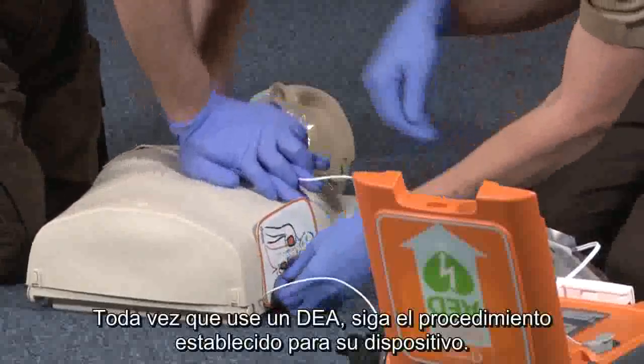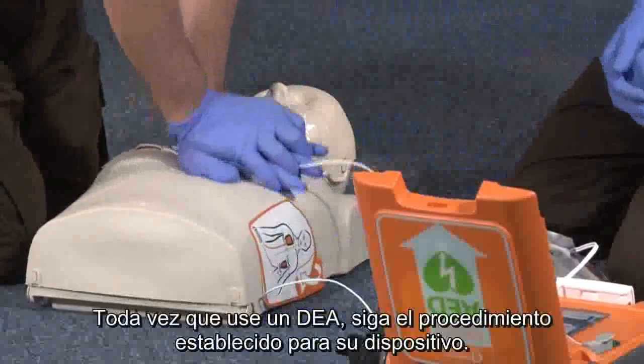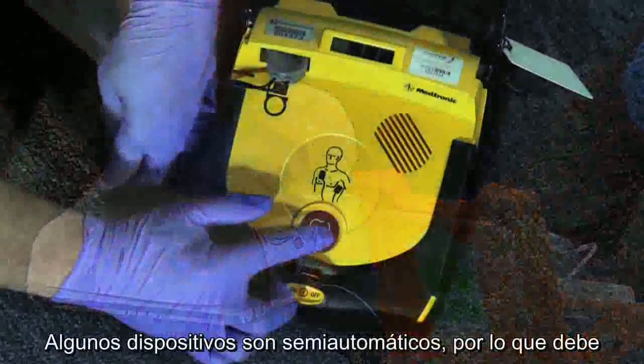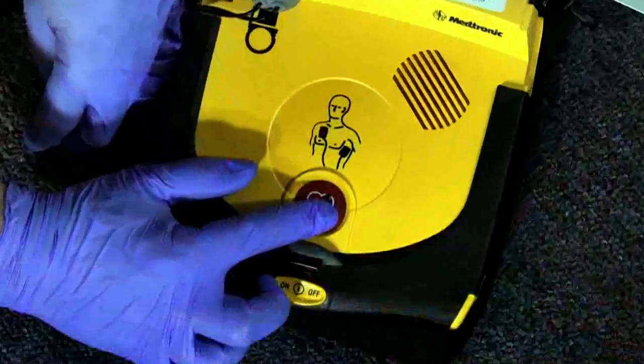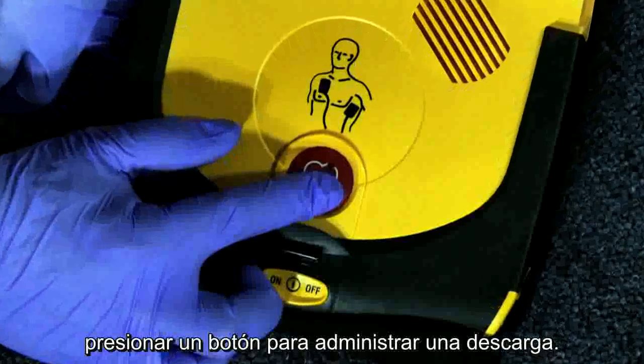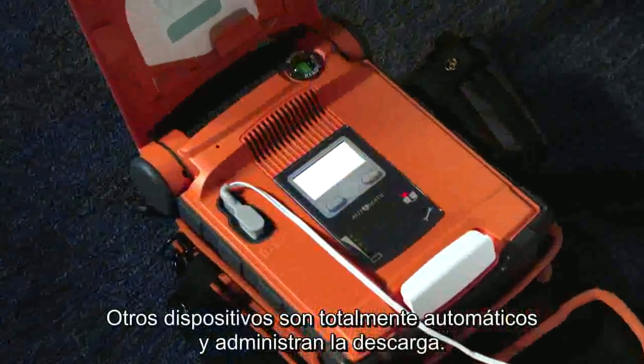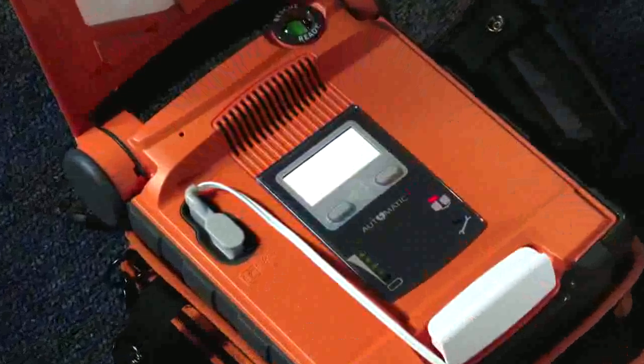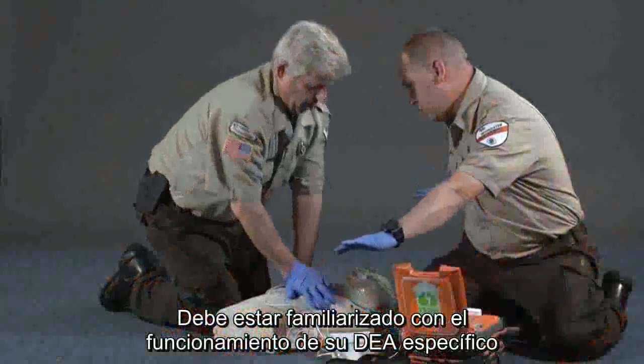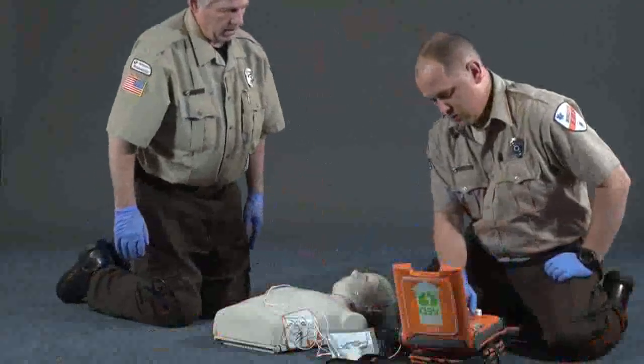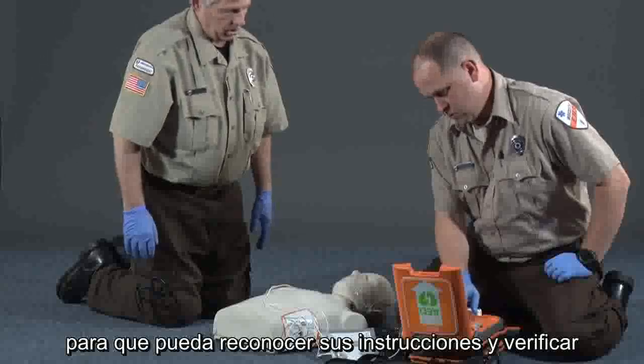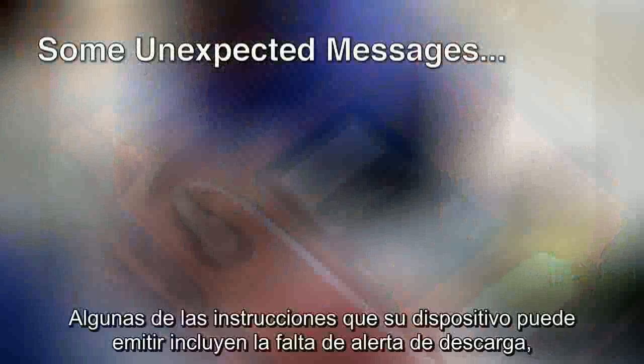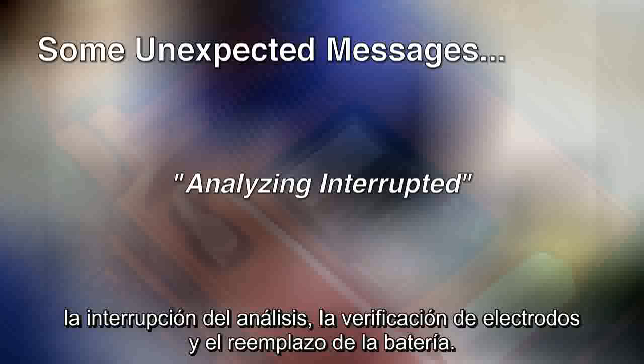Whenever using an AED, follow the established procedure for your device. Some devices are semi-automatic, requiring you to push a button to administer a shock. Other devices are fully automatic and administer the shock. You should be familiar with the operation of your specific AED so you recognize its prompts and can check or correct unexpected messages.